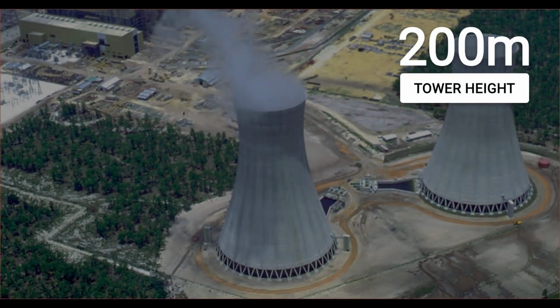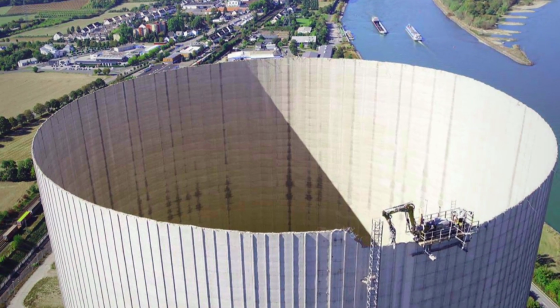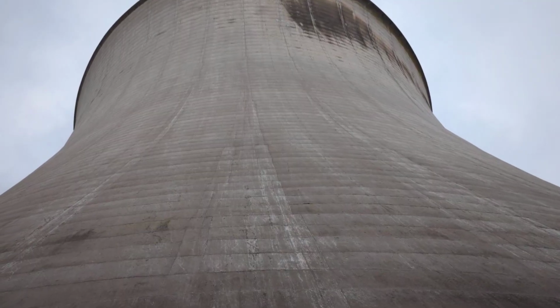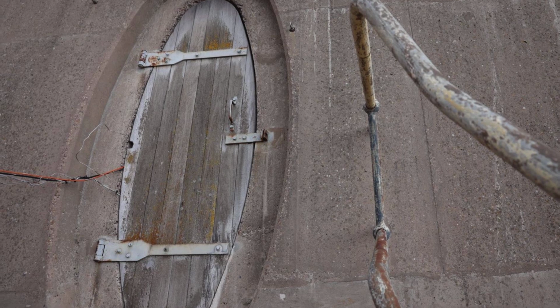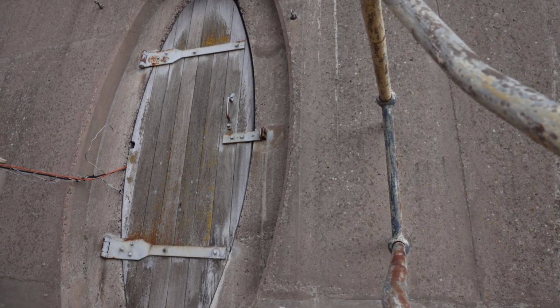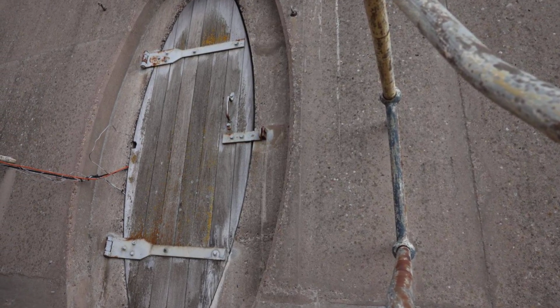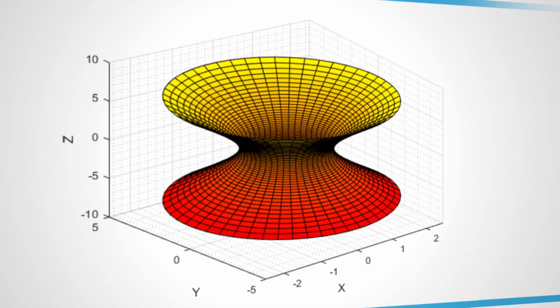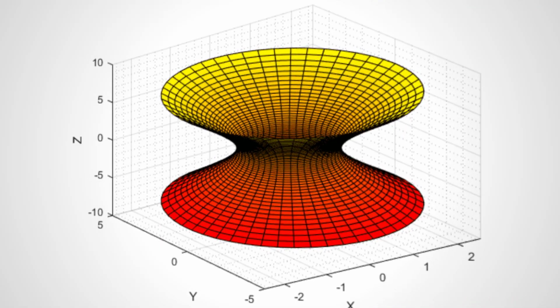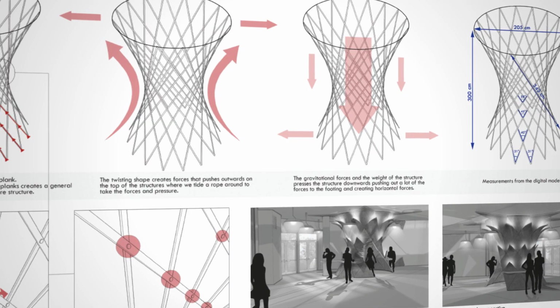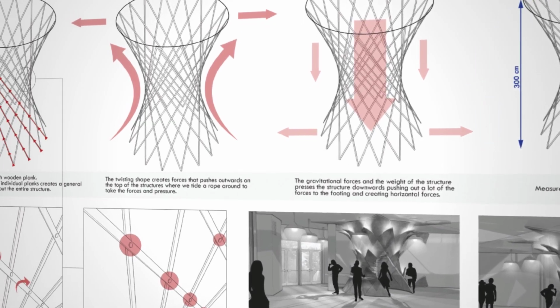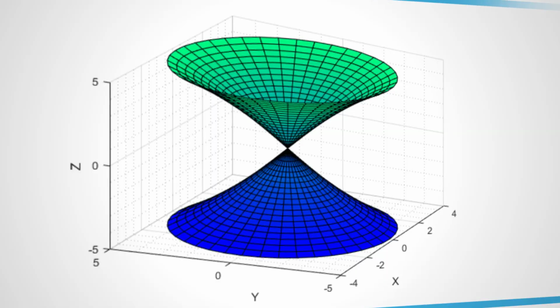The largest natural draft towers can exceed 200 meters in height and 120 meters in diameter. Furthermore, the walls are designed to be as thin as possible. Less material means lower cost and more area for airflow. However, a very tall cylinder with thin walls would be inherently weak, akin to a large, empty beverage can. The double curvature of a hyperboloid, however, stiffens the shell against both vertical loads, like the structure's own weight, and horizontal loads, such as wind.